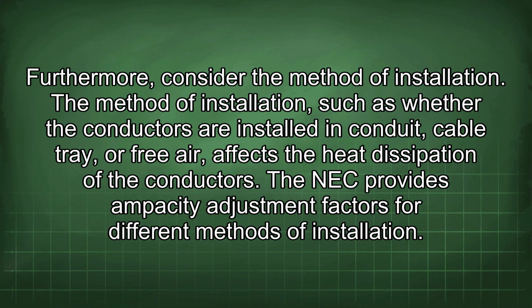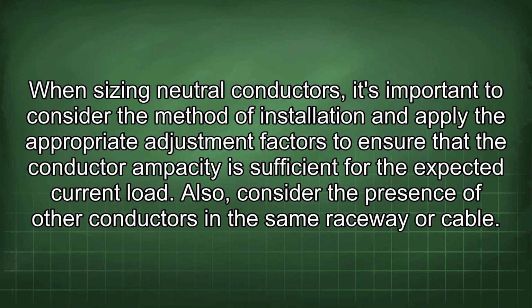Furthermore, consider the method of installation. The method of installation, such as whether the conductors are installed in conduit, cable tray, or free air, affects the heat dissipation of the conductors. The NEC provides ampacity adjustment factors for different methods of installation. When sizing neutral conductors, it's important to consider the method of installation and apply the appropriate adjustment factors to ensure that the conductor ampacity is sufficient for the expected current load.